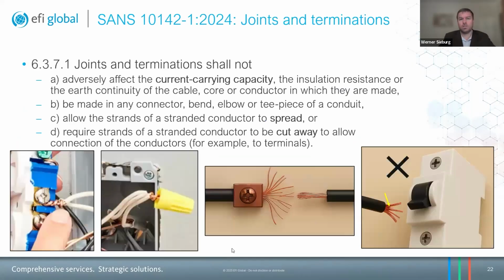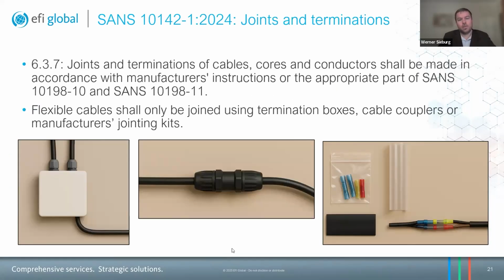Right, flexible cables, which are the three cables that you see below, shall only be joined using termination boxes, cable couplers, or manufacturer's joining kits. So on the left is the termination box. Once again, non-flammable, non-thermally conductive. Cable couplers, which, in the context of solar installations, you guys might know as the MC4 connector. But this is basically just a purpose-built cable coupler, which also connects to both ends of the cable using a crimp, right? Which is also indicated on the right.